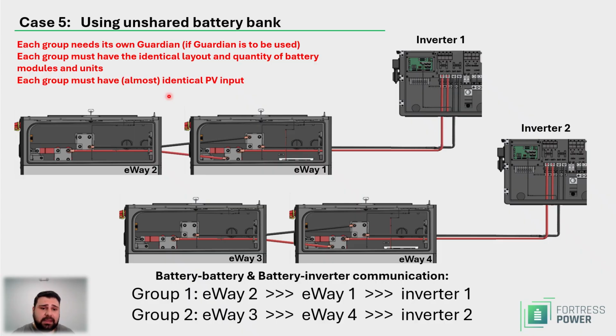So inevitably the battery group that was receiving less charge power will discharge faster, meaning you're going to lose part of your, or partially lose your, power output capacity, and you will lose part of your storage capacity. We want to avoid that. We want to have even charge and even discharge, and that's why we're saying each group must have at least almost identical PV input. Ideally, you go for identical PV input, but when the cloud flies over, maybe the PV strings that connect to inverter 1 are partially covered or something, that's fine. But in terms of the strings themselves on the paper, as a target, they must be identical.